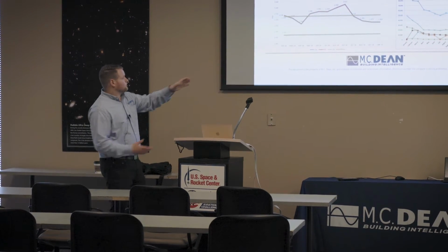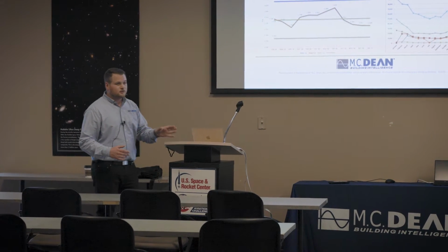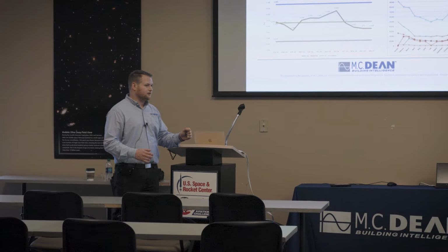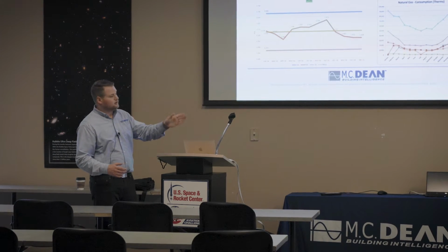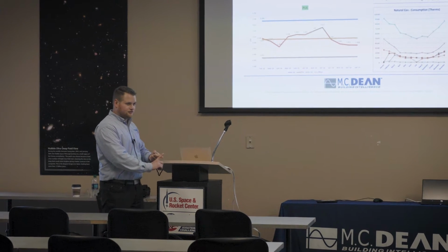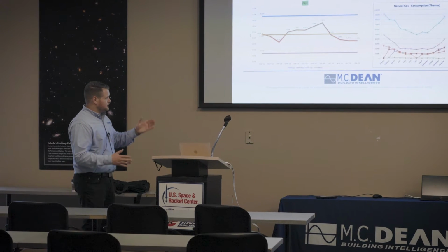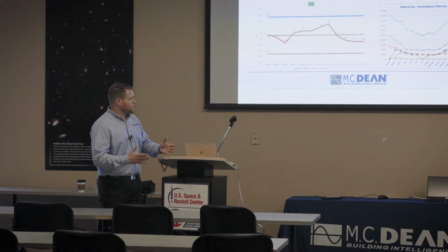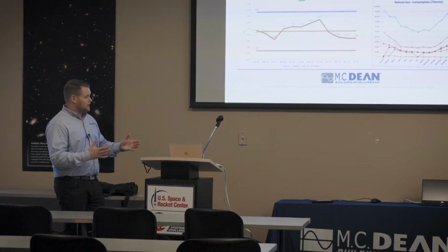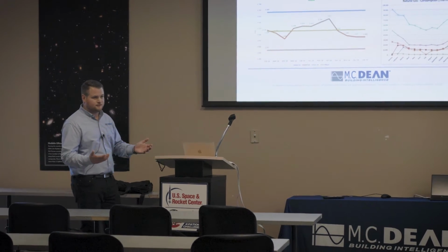So on the left, or your right-hand side, you can see electrical and natural gas from one of our facilities. What we've done here is we pulled the utility bill information, and we're trending year over year based on our usage data from that, and we compare it to the design standard of the facility and the Energy Star LEED rating of the facility as well. So we can see from this trend that we're operating well underneath the Energy Star standard, the design standard. We're well within our limits for our LEED facility.